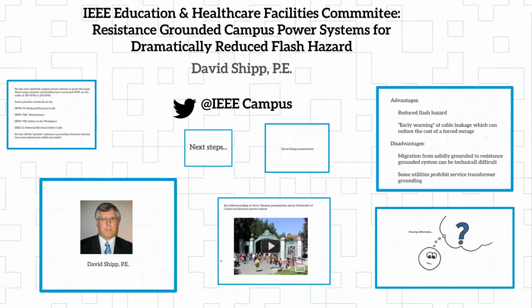So I got to think, we need to change the system and design either high resistance grounding, put in isolation transformers. We need to use some of these to get the incident energy down real low and at the safety. Once I do the isolation transformer for, say, I have 277 volt lighting, I'll do a 15 kVA delta 480 to 480/277, feed the one lighting panel, small kVA, feed the local lights locally, and then all the neutrals go away, and on the 480 volt, the utility side, I can then high resistance ground, and I've eliminated the requirement for doing that. And they say we can't afford it.